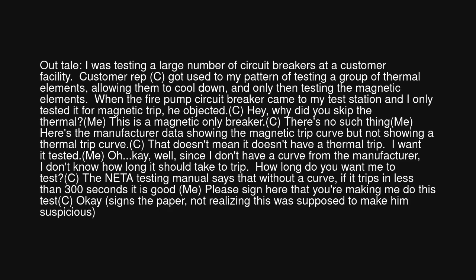C: That doesn't mean it doesn't have a thermal trip. I want it tested. Me: Okay. Well, since I don't have a curve from the manufacturer, I don't know how long it should take to trip. How long do you want me to test? C: The NETA testing manual says that without a curve, if it trips in less than 300 seconds it is good. Me: Please sign here that you're making me do this test. C: Okay. Signs the paper, not realizing this was supposed to make him suspicious.